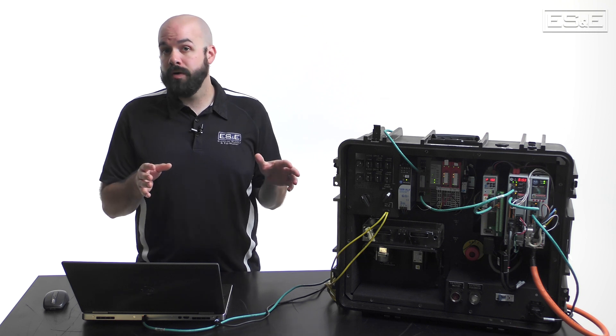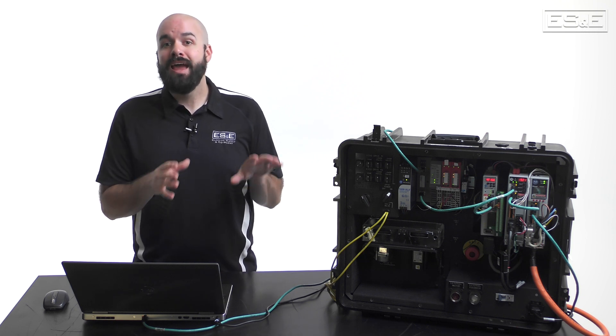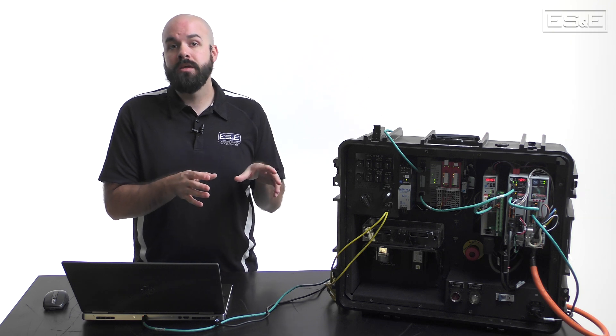The merge and merge speed fields allow you to take over full control of the axis with this MAJ. If merge is enabled, then any other currently running motion instructions will be stopped, and this MAJ will control the action of the axis going forward. There are also four status indicator bits, and none of these bits tell you anything about the current state of the target axis — they're only diagnostics associated with the given instruction.